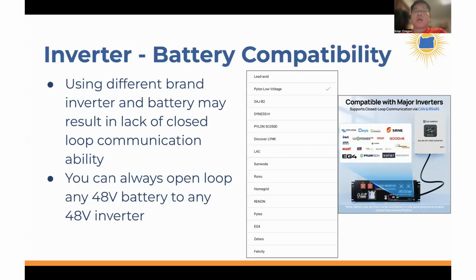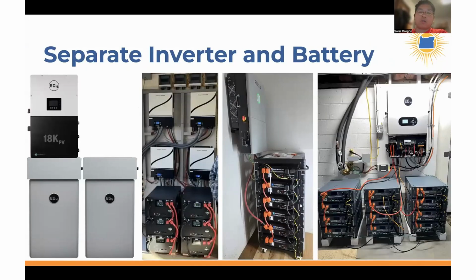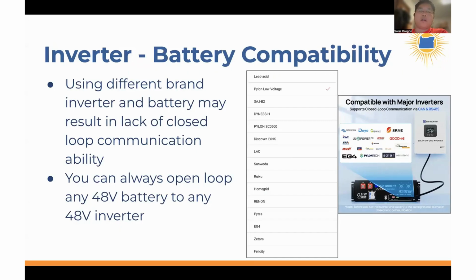Closed loop communication means the inverter knows very precisely the state of charge of the battery, its temperature, the number of amps it's discharging or charging, and the state of charge of every single battery. In some of these pictures there are 6, 9, or 12 batteries, so instead of the inverter only knowing the average power of the entire battery bank, it knows the power and voltage of every single individual battery in that rack. That's what you gain with closed loop communication.